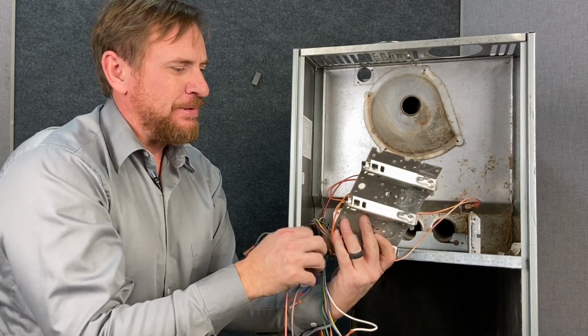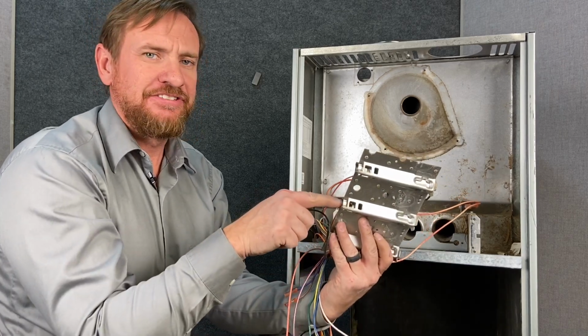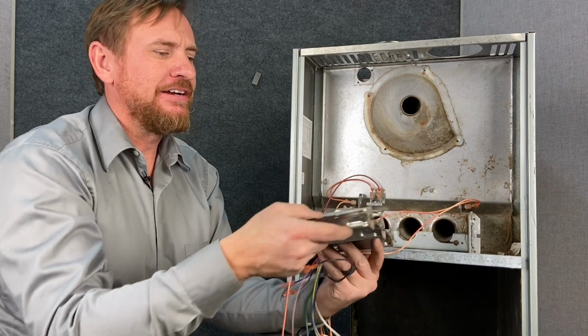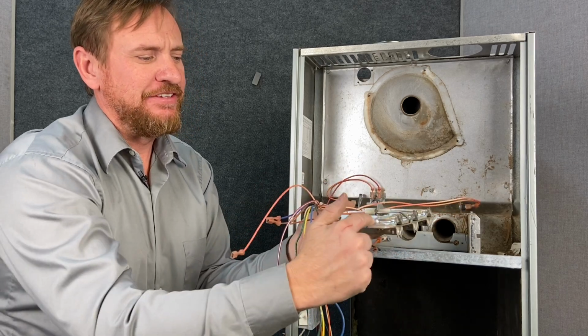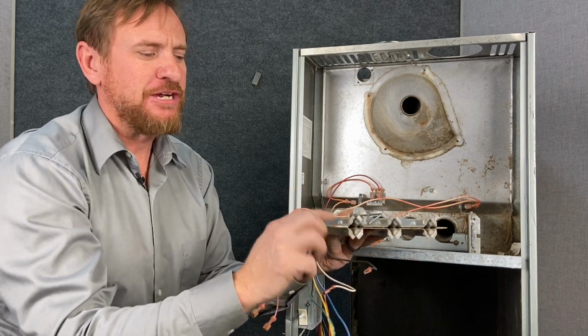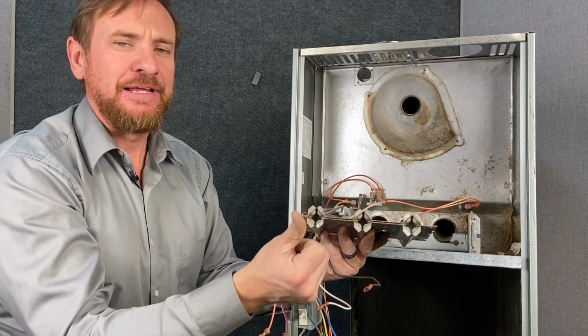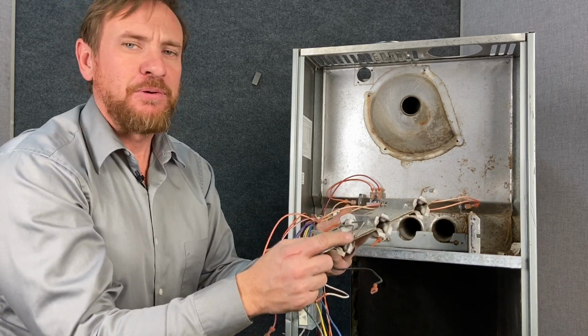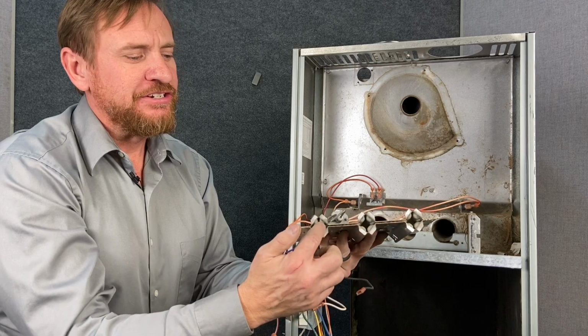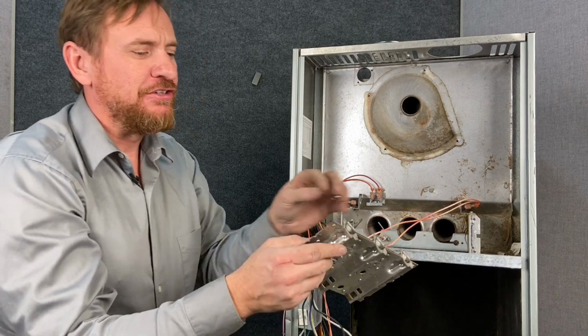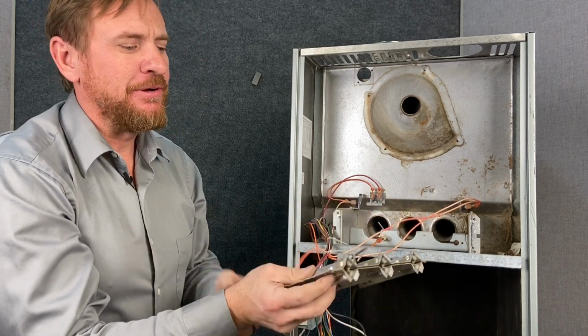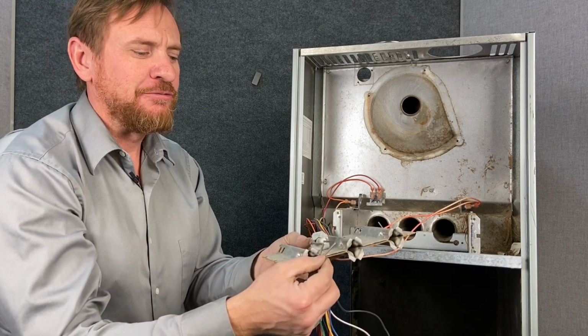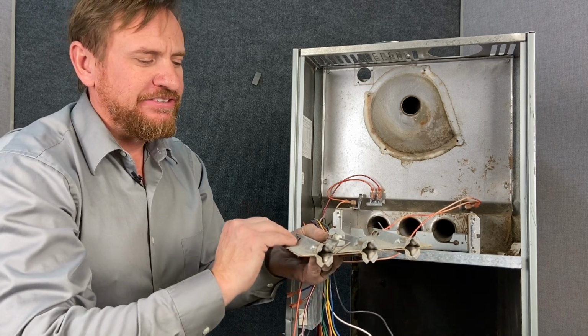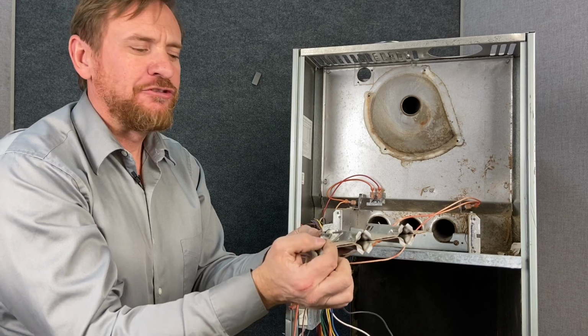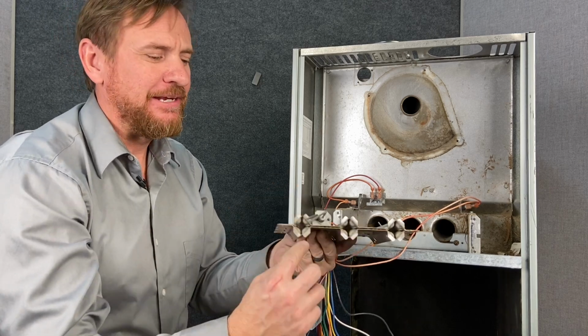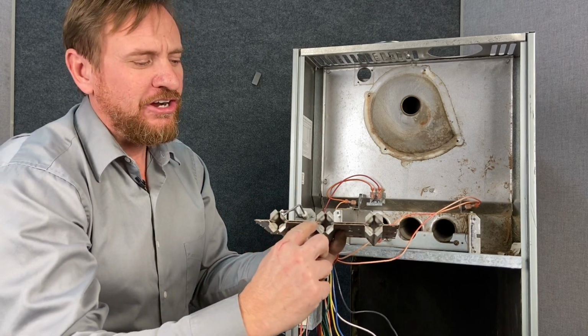The jets or the spuds shoot the gas in the center here, mixed with primary air, mixes it inside of this tube, or these in-shot burners, and then it directs that flame towards the heat exchanger. Here's our spark igniter. So we're going to send our gas across the spark igniter. If you notice, the spark igniter here has a little bit of a burnt spot because the flames are always burning against it. The idea is if we send gas through here and we're arcing a spark across here, it ignites that flame.